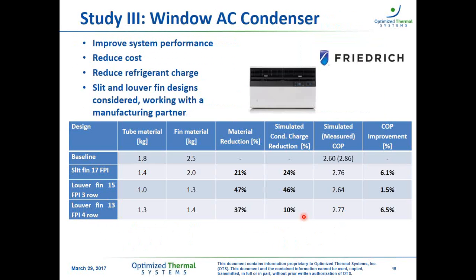Now, the last study is a window AC condenser as well, focusing on COP improvement, material reduction, and charge reduction. Here we have on this table a baseline and 3 novel designs using small diameter tubes with different fins. And we can see from 20 to 50% reduction in material and 10 to 50% reduction in refrigerant charge, while still improving the overall system COP by up to 6 to 7%.